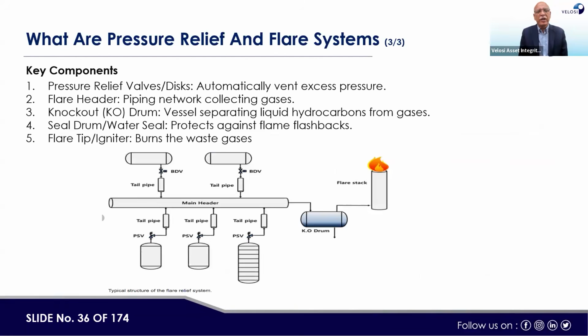As for the components, if you see here, for example, these are the PSVs, which in case of high pressure will open. This is the main header of the flare or relief system. Then there are the BDVs, the blowdown valves, and these are opened with the help of the ESD system. Then this fluid all goes to a flare knockout drum and you can burn it. So these are the components of any relief system and flare system. This part is the relief system and this part is called the flare system.